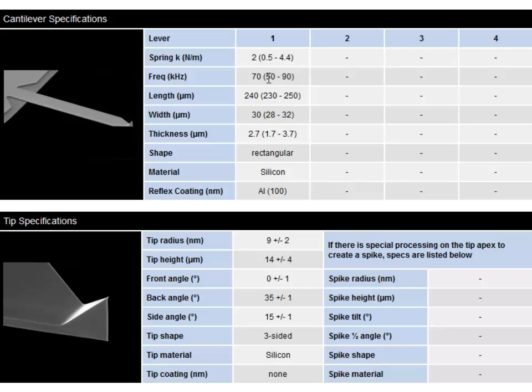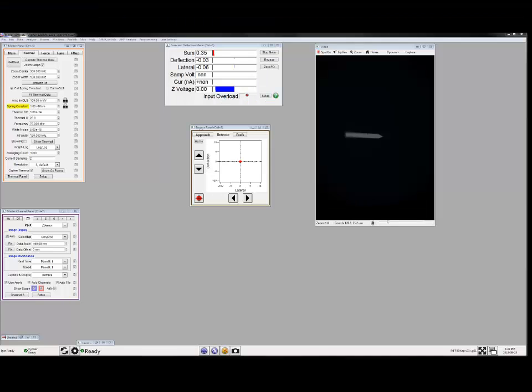So now let's take a look at the software. What I've already done is I've loaded one of these AC240s into the Cypher AFM. I can see the AC240TS in the video window here, and I'll start by lining my laser up onto the cantilever using Spot On. Right-clicking on the cantilever puts the laser on there, then of course I have to zero my photodetector. I'll activate the software method by going to the Thermal tab and pressing the GetReal button.